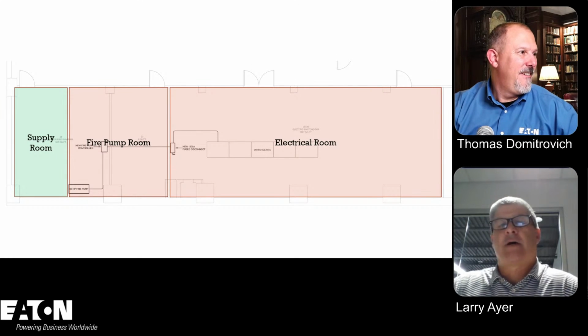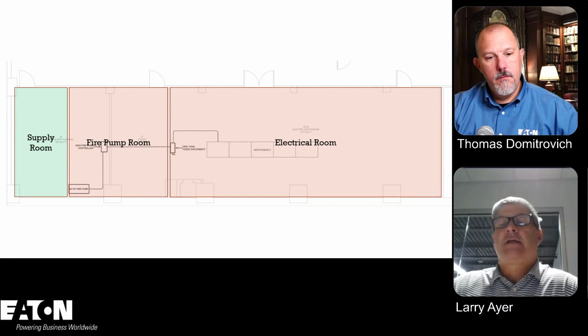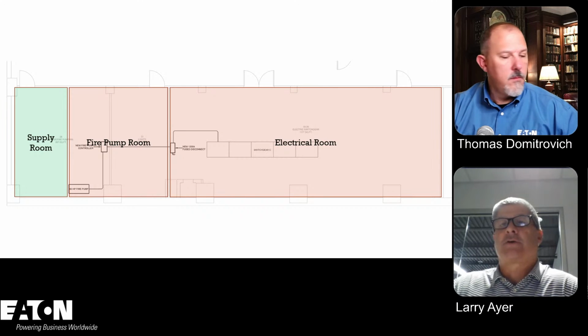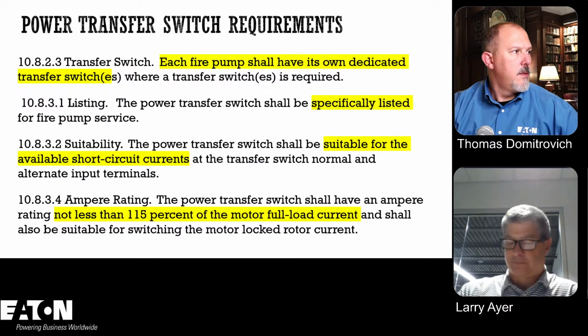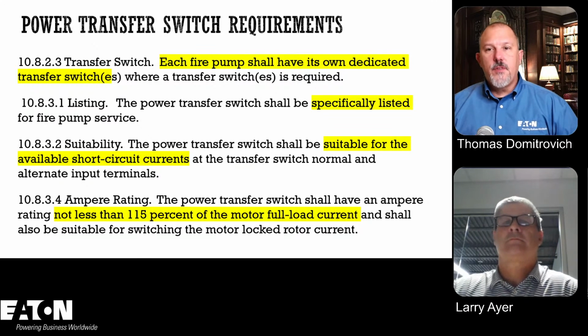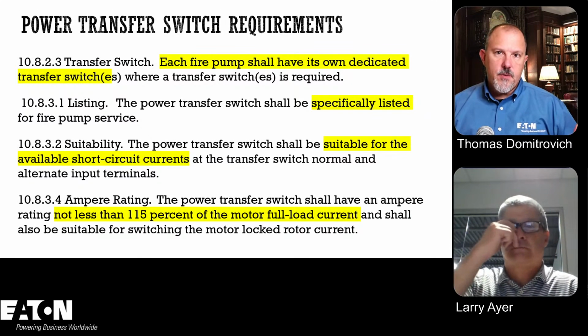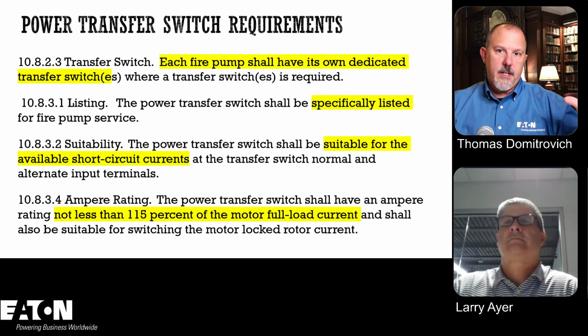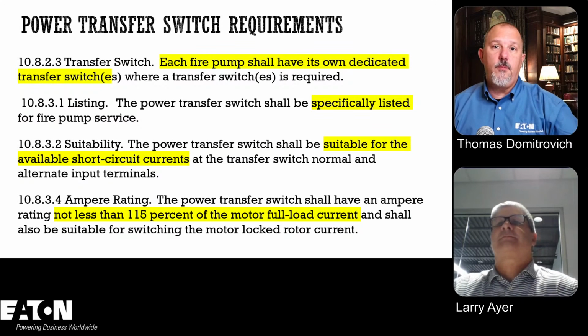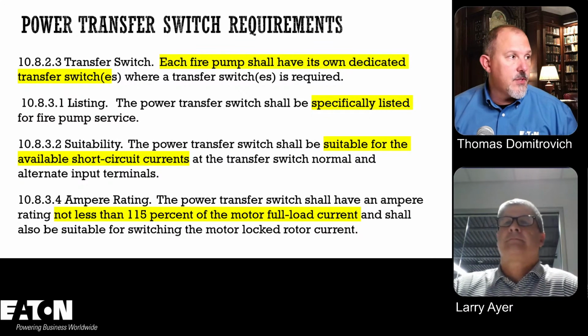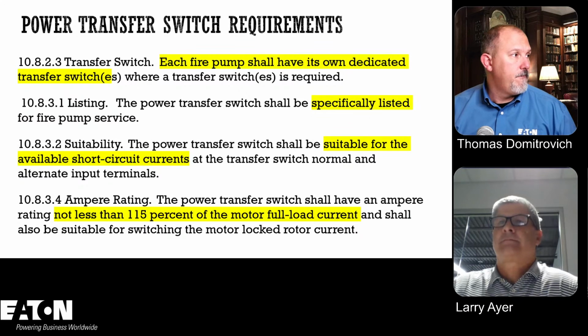Now there's one question that just came up. It says, does that rating apply to an emergency feeder from a genset? And yes, that would also require you to run that in a 2-hour rated cable or listed assembly. All right, so now we're getting into the transfer switch discussions, because if I have a transfer switch, that means I have 2 different sources feeding this fire pump, and I've already made the decision that one is not as reliable as I need it to be. So now I have an alternative source, and that's when I get into my transfer switch.